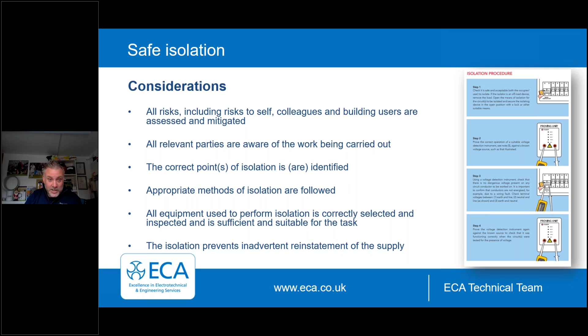And we have to ensure that the isolation that we put on these circuits prevents inadvertent reinstatement of the supply. So someone just can't go there and turn that back on. So, we all know the basics: locking off, checking our equipment, prove the isolation, recheck our test equipment so it hasn't failed. It takes seconds but can save lives. So it's better a dead circuit than it is a dead person.